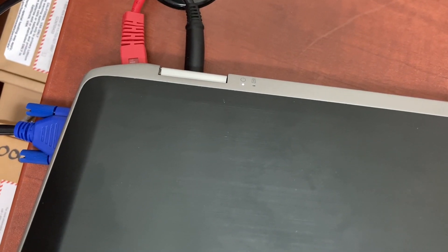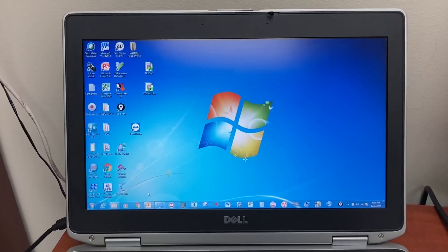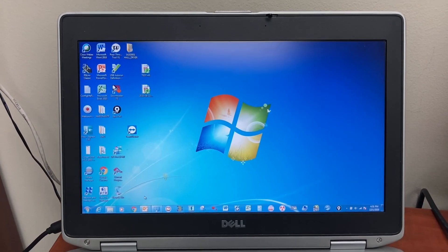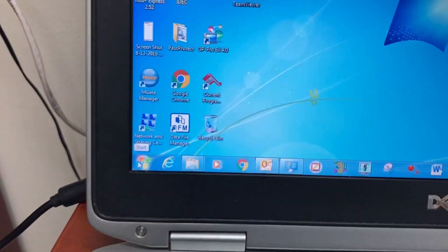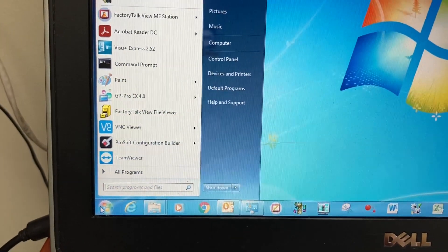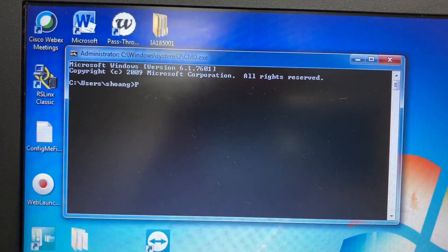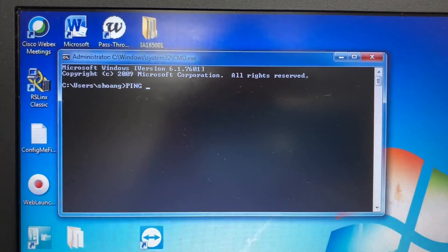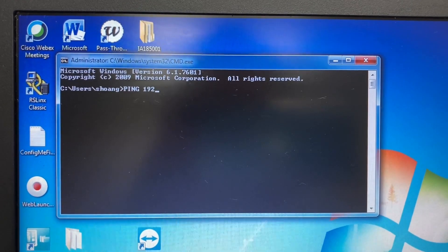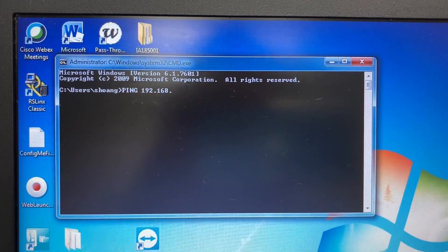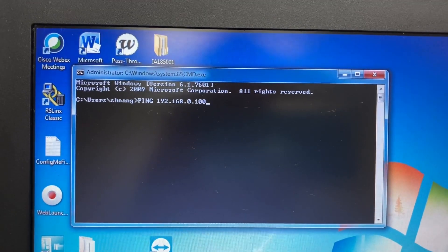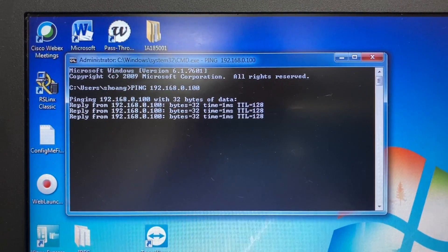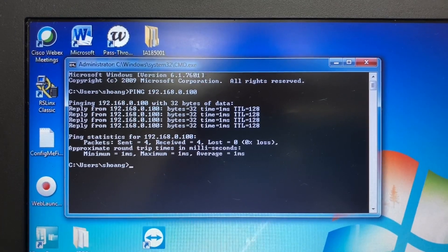Connect the HMI to the computer with an Ethernet CAT5 cable. To check the connection between the HMI and the computer, go to Start and type CMD. Then ping the HMI IP address: 192.168.0.100. The connection is good with 0% packet loss.